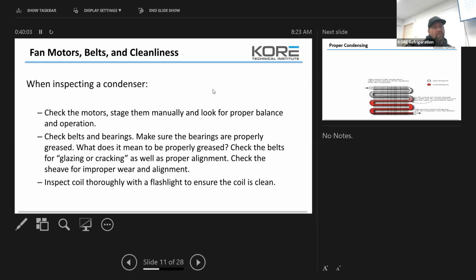Inspect the coil thoroughly with a flashlight to ensure the coil is clean. I can't tell you how many times guys walk up and say, yep, it's good. You've got to shine through the coil, because a lot of times they'll brush the front and it'll be impacted with dirt two or three runs back. And that coil could be 3 to 5 runs deep, depending on the type of equipment, and even more on supermarket condensers.